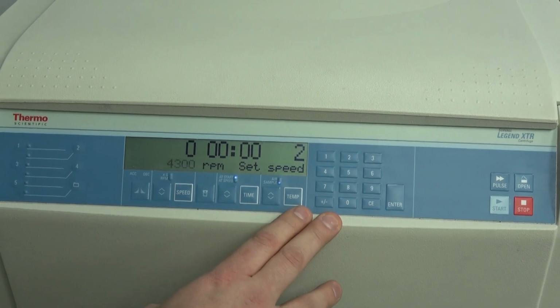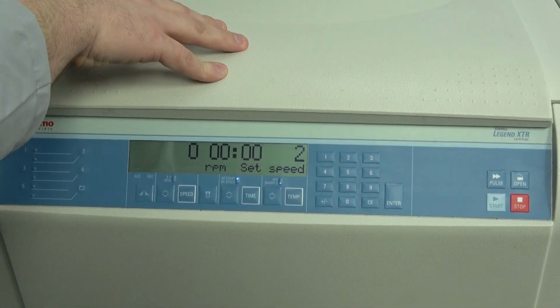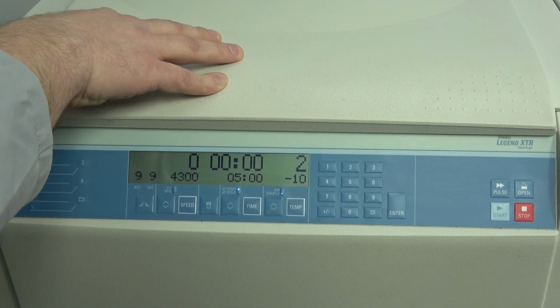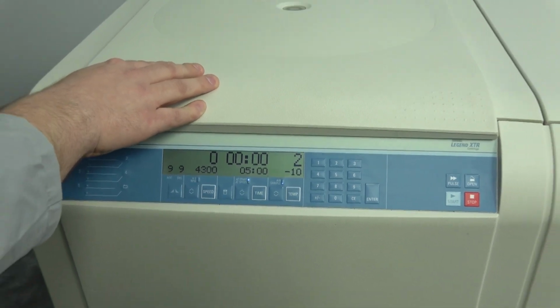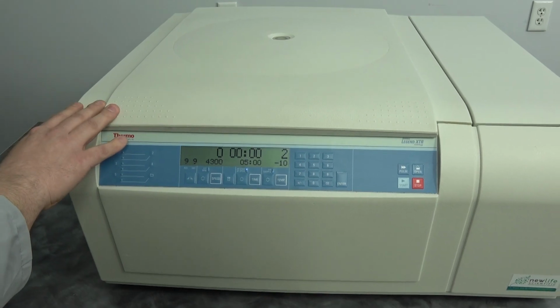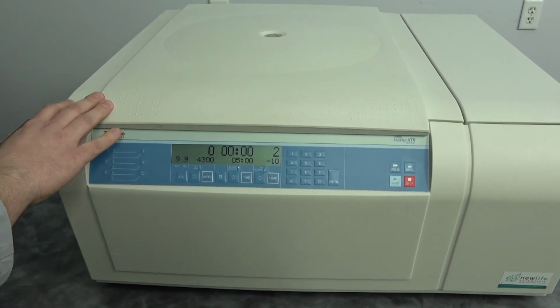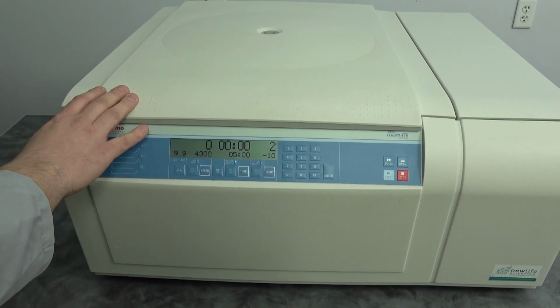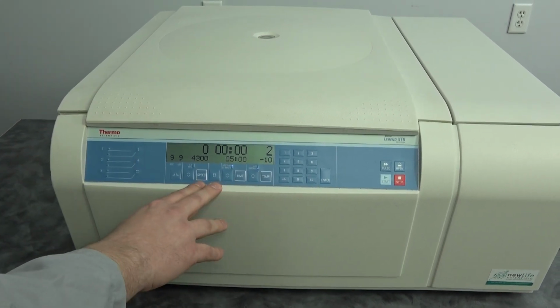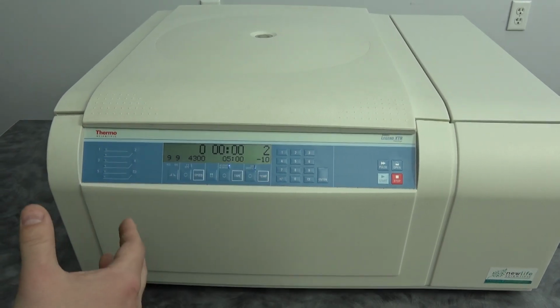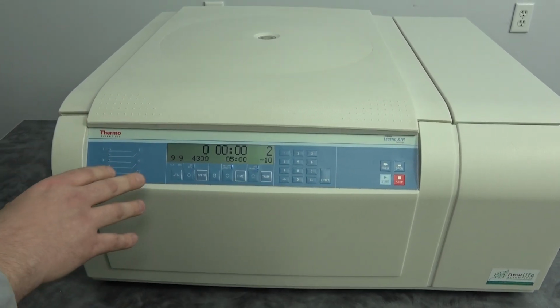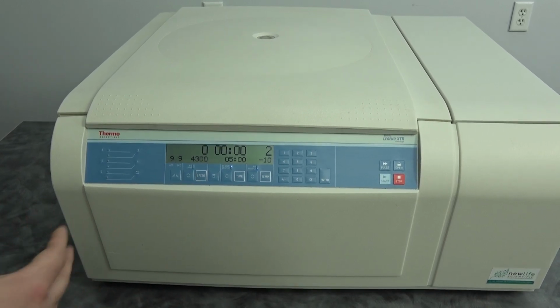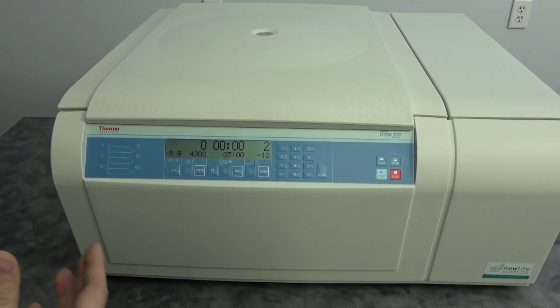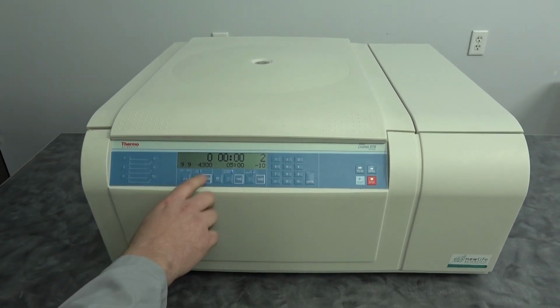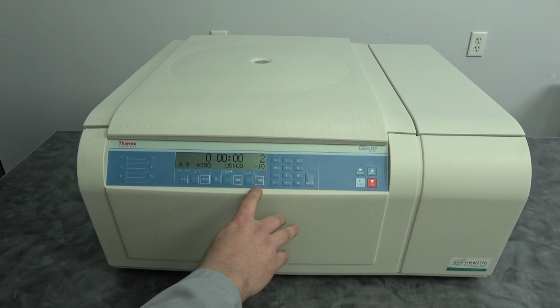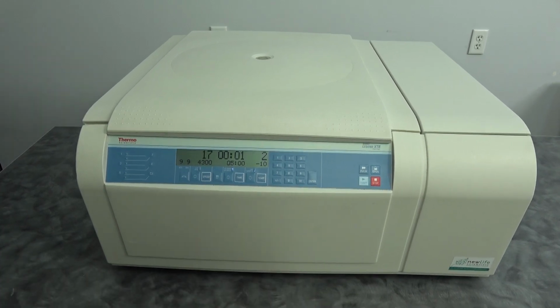Now, one of the key things to note is that, yes, that rotor, if you looked, said that it would reach 4,700 RPMs. That is the rotor max, but that is not the speed that you can run that rotor in this centrifuge. Again, checking your manuals for the specifications on what you can do is very important. That's going to help you prevent overrunning your rotors. And actually, there are a lot of safety features on these now where it will actually prevent you from running rotors beyond its speed requirements. So make sure you're getting those details from your manual as well. So now that you have your speed set, you can set your time, you can set your temperature, but from there, you just hit start.